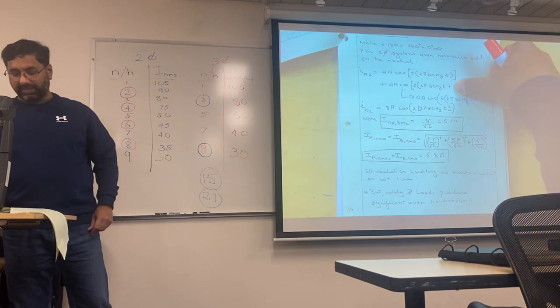So that's my thing, and then see this? I double the current. So that's what I'm saying, you have to double the current, not triple. It's double the current. Having said that, when you look at the RMS of 8 ampere, you end up with 5.7 amps in the neutral.